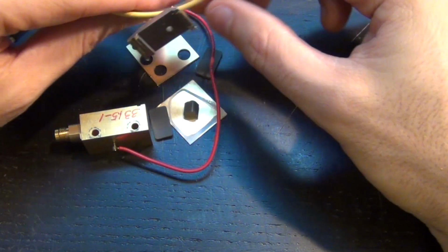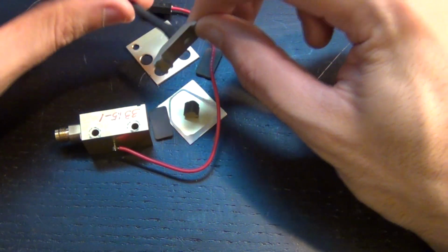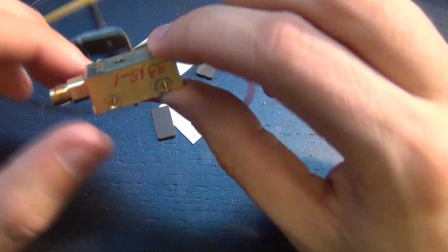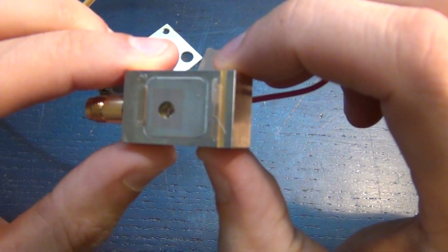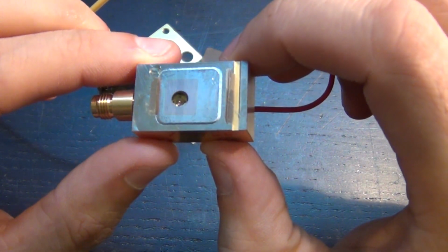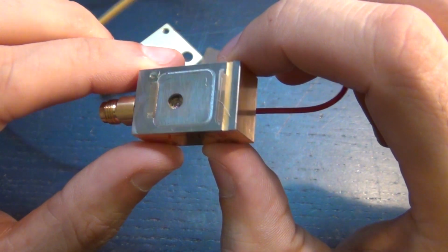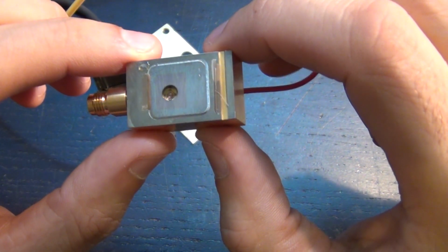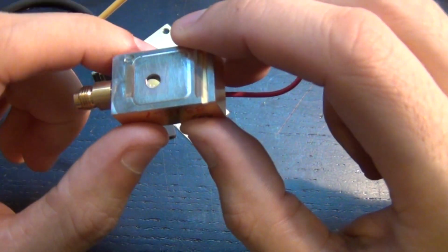So I take back part of what I said. I thought the collimator was built into this portion of the module, but it's not. Interestingly enough, it's built into here. Look how cool this thing is. It's just crazy how they've built this with this optical window and the tiny lens that you see here, which focuses the light onto the photodetector.